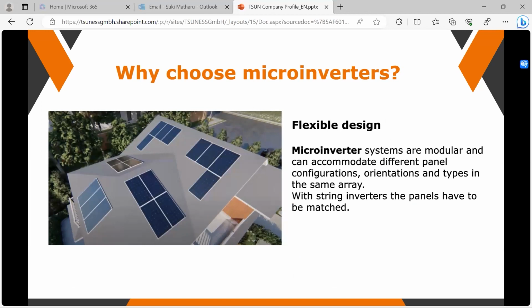Microinverters also give you the flexibility of design. Panels don't have to be facing in the same direction. The orientation could be anywhere, facing northeast or west, because they all individually have their own MPPT. We'll be tracking their IV curve no matter which direction they are in, rather than relying on a string. It doesn't matter what type of panel it is. So in 10 years' time, if the panel fails or has issues, you could easily remove it and replace it with any panel that fits within the microinverter's specifications. You'll always be able to find something out there that fits that spec.